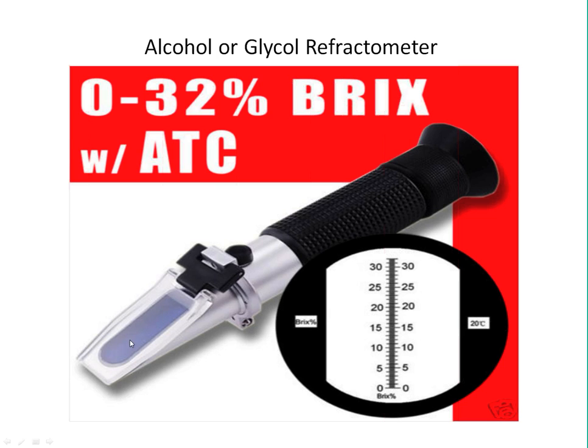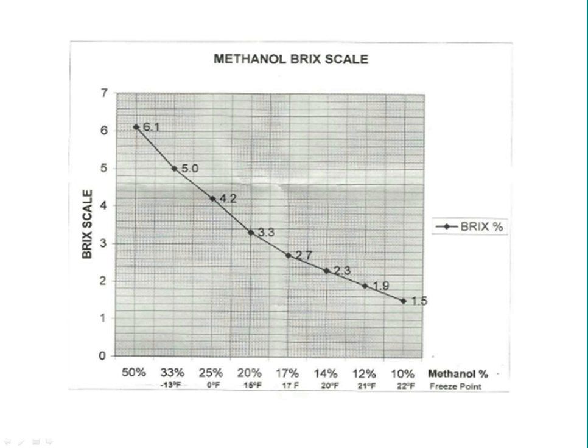You simply put a drop of your sample fluid here. If you look on your screen, follow my cursor, you'll lift up this cover. You'll put a sample via an eyedropper here on the screen. You'll close that lid, and then you have to have some pretty darn good light to be able to look through it, and you're going to see the indication on the BRIX scale. That is how they're measuring that alcohol content or the glycol through the refractometer.